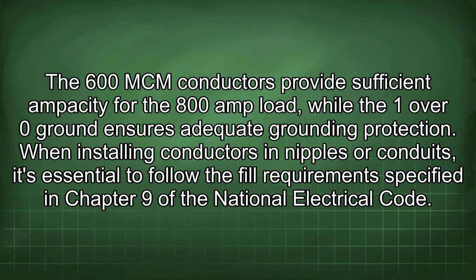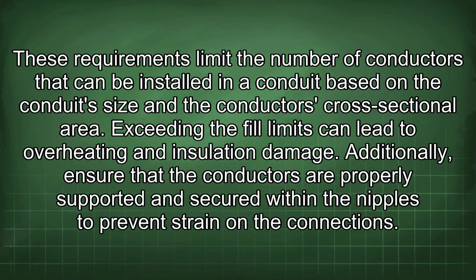When installing conductors in nipples or conduits, it's essential to follow the fill requirements specified in Chapter 9 of the National Electrical Code. These requirements limit the number of conductors that can be installed in a conduit based on the conduit's size and the conductor's cross-sectional area. Exceeding the fill limits can lead to overheating and insulation damage. Additionally, ensure that the conductors are properly supported and secured within the nipples to prevent strain on the connections.